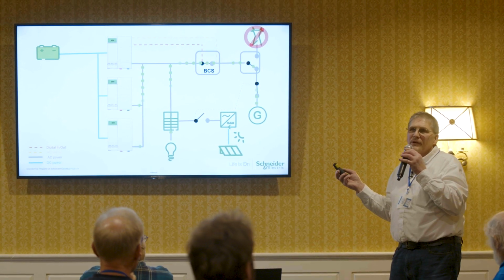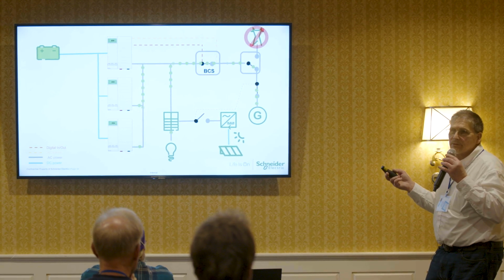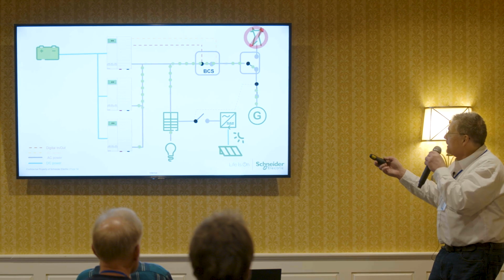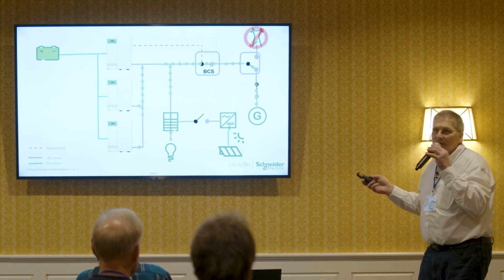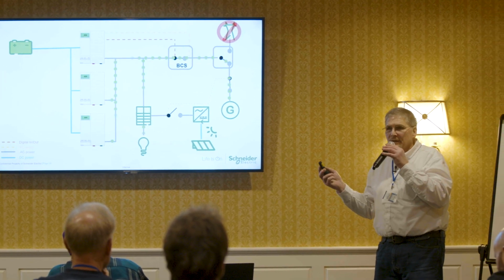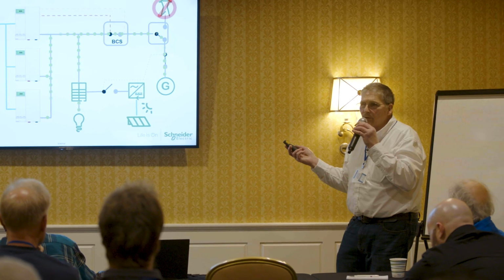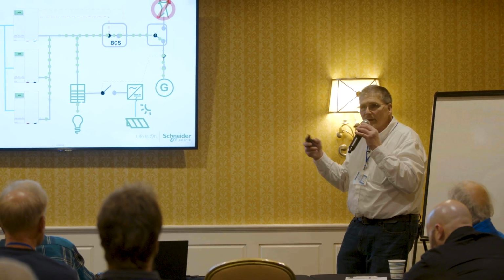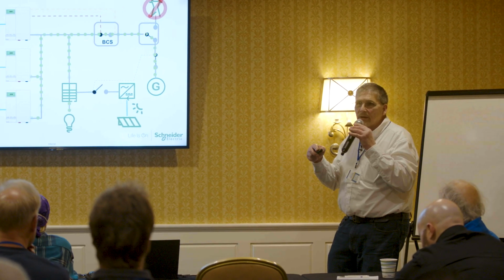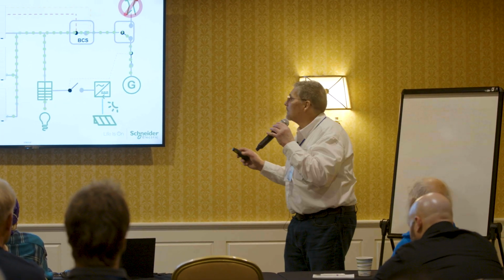You should never install XW Pro without Insight Home. Does it require the AGS also to control the generator? Yes, I mean you could use the aux port of one of the slaves, but the nice thing about the AGS is it allows you to program the cool down cycle. A lot of times you want to let the generator run for a period unloaded before you actually stop it.